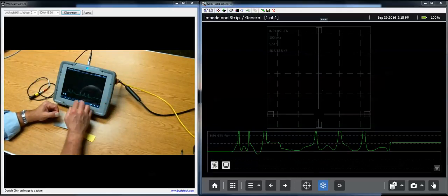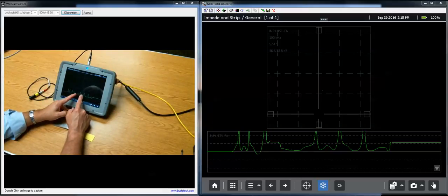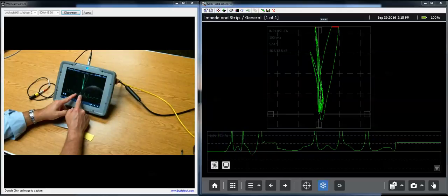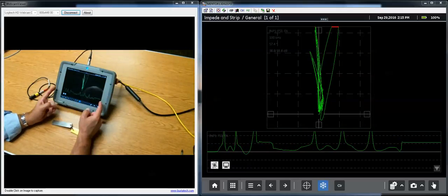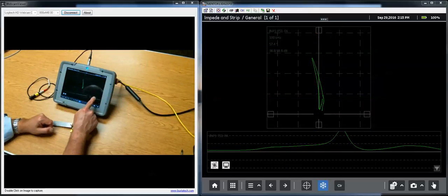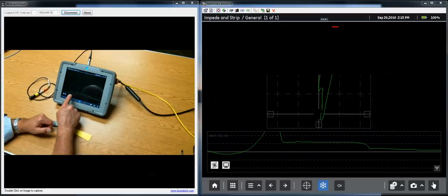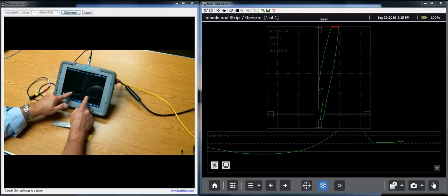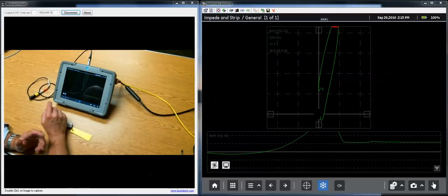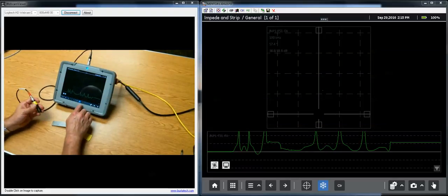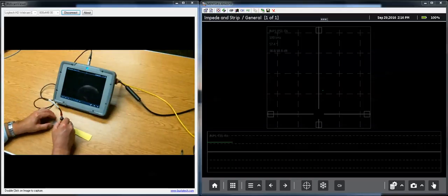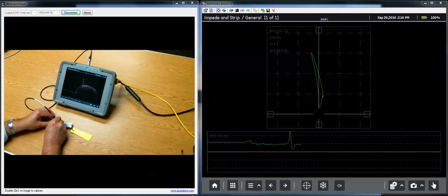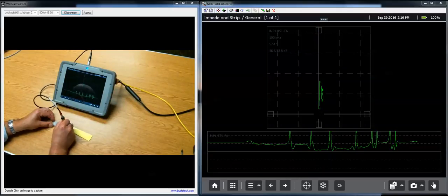You can close the overview and just look at your strip chart. When you're in this mode, again the pinch gesture will put cursors down very close to the ends, but now I can continue to stretch that out, swipe side to side, center up an interesting indication, look at it. Okay, I've evaluated that. Double tap, there you are, I'm back to normal. I can clear that by hitting the clear button. I can turn freeze off and now I can come in and inspect live.